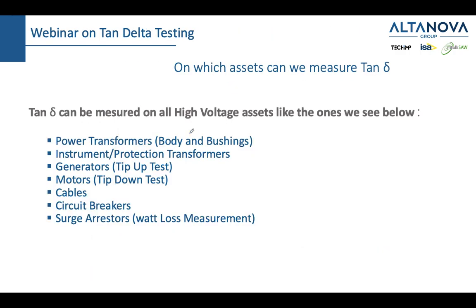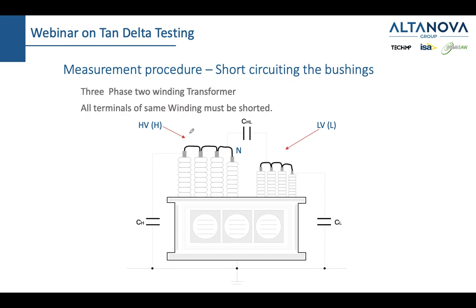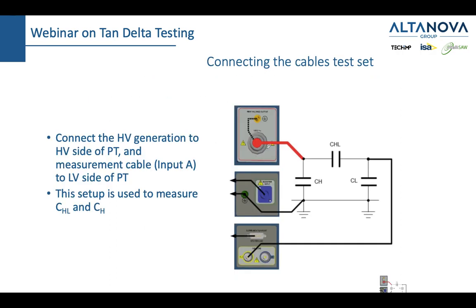Why is this so? Well, this is a good thing, because when you do a tan delta measurement, you don't just get one number. You get minimum three numbers. And it's good because maybe all of them are okay, but maybe CHL is good and CH is good, but CL is bad, which means the insulation between the low voltage and the ground is not good. So you have some indication of what needs to be fixed. When you do some other DC test, you just get one number, and that one number cannot tell you where the problem lies. Here you get minimum three numbers, and effectively you will get nine numbers, or even maybe 11, because you will also be testing each bushing by itself. So after you have short-circuited, you need to connect the cables.